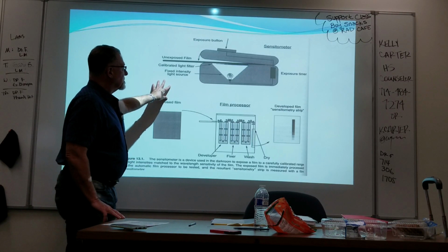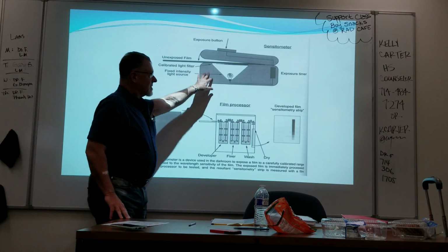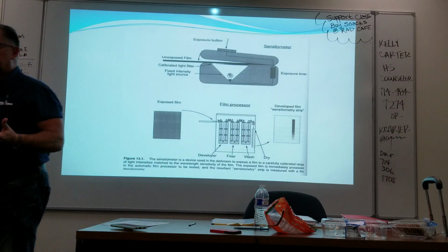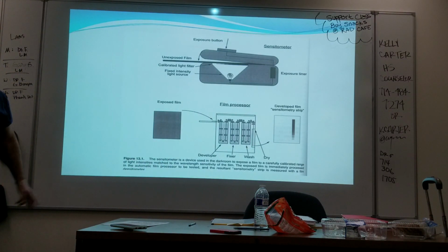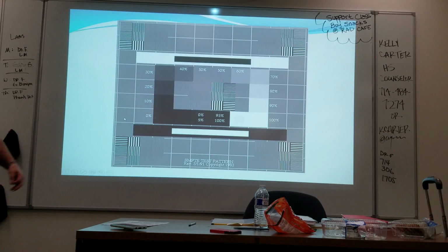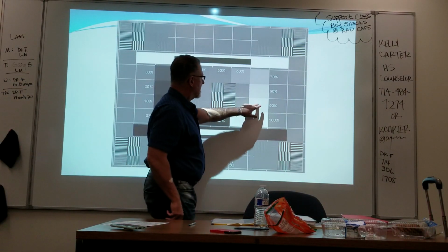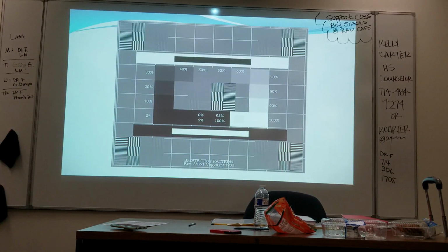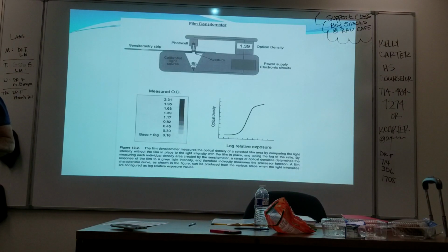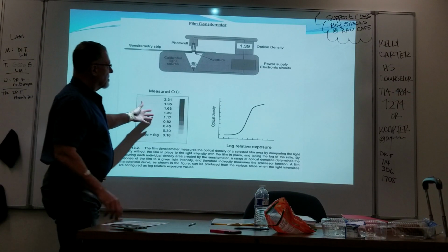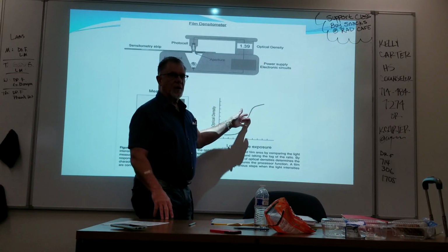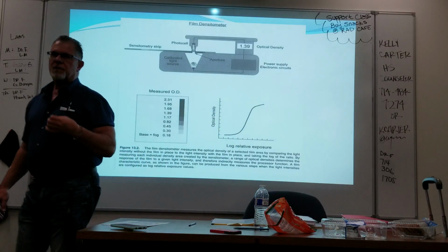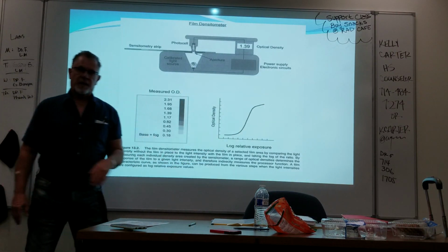And you can use, like we used to do, a sensitometer like we did on film and actually plot these on a graph and see what those look like. So remember, in film you get this typical H&D curve. But for a calibrated digital display, this should be a straight line.